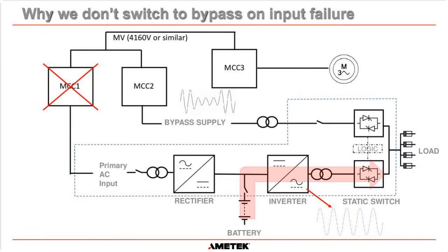And here's an example, a good schematic of what that means. You can see at the top here, that's the main HV bus, and you can see that it's been tapped off here. MCC2 is where the bypass is fed from. MCC1 is the MCC that's failed, but remember, we've got MCC3 connected to this HV bus as well. And that has loads of three-phase motors connected to it.